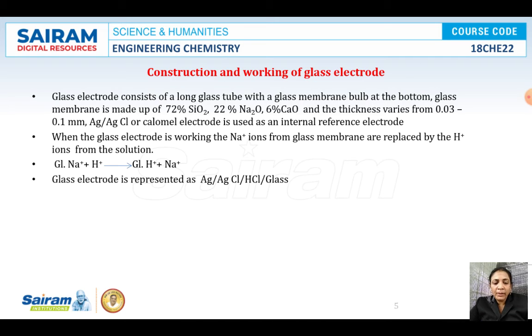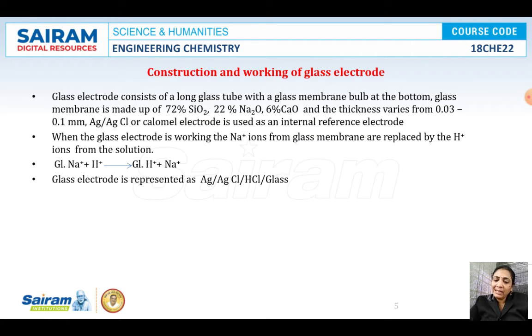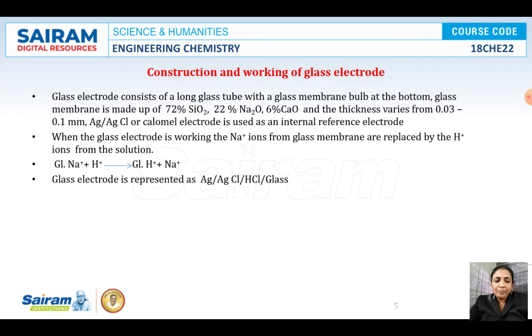At that time, it should be calibrated by dipping the electrode overnight in a known pH solution — for example, pH 7 or pH 4 — for 24 hours. Then the electrode will become completely recharged with Na+ ions and will start working correctly. The glass electrode is represented as: Ag/AgCl | HCl | glass.